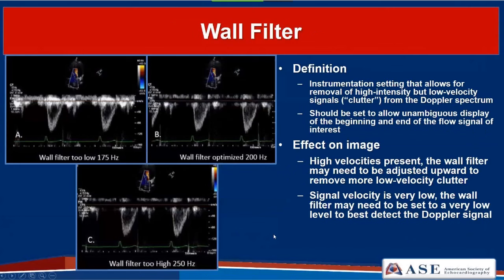The wall filter is an instrumentation setting that removes high-intensity but low-velocity signals or clutter from the Doppler spectrum. It should be set to allow unambiguous display of the beginning and end of the flow signal of interest. If velocities are high, the wall filter may need to be adjusted upward. If signal velocity is very low—like in perfusion studies—the wall filter may need to be set to a very low level. For example, looking at a pulse-wave Doppler signal from the LVOT: with the wall filter set too low, there's clutter along the baseline making timing of the waveform difficult; optimized at 200 Hz, the beginning and end of the waveform are clearly visible.